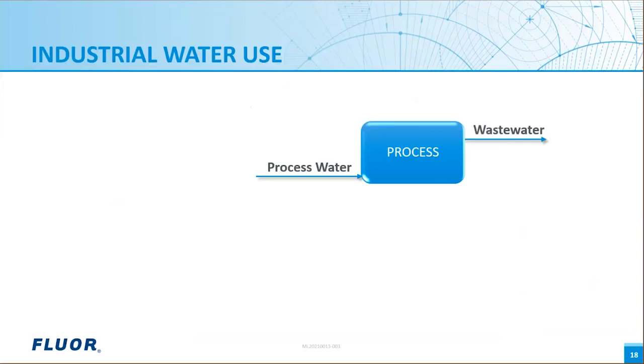As we put water in contact with a process, we have to deal with the resulting effluent or process impacted water. The level of contamination and effluent quality will drive the treatment process, whether the wastewater is discharged to the environment or reused in the facility. When it comes to reuse, the cooling tower system is usually the best place where we can dispose the largest amount of water with the lowest quality. So this represents the best opportunity or lowest hanging fruit, if you will.